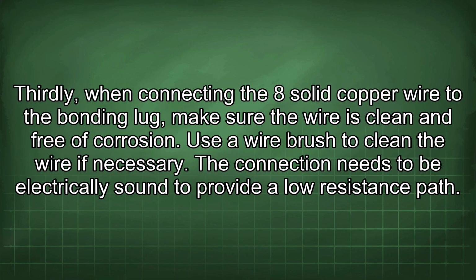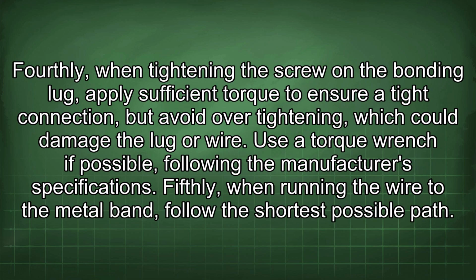Thirdly, when connecting the 8-solid copper wire to the bonding lug, make sure the wire is clean and free of corrosion. Use a wire brush to clean the wire if necessary. The connection needs to be electrically sound to provide a low resistance path. Fourthly, when tightening the screw on the bonding lug, apply sufficient torque to ensure a tight connection but avoid over-tightening, which could damage the lug or wire. Use a torque wrench if possible, following the manufacturer's specifications.